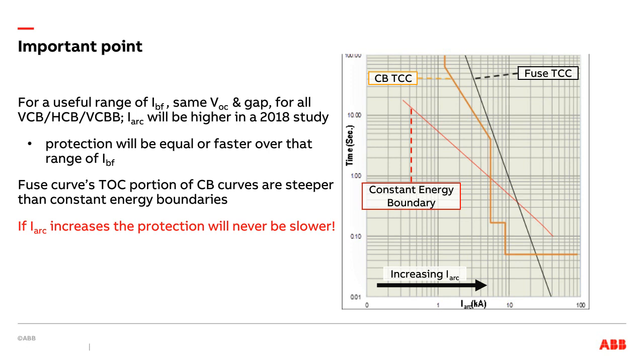You kind of need to analyze more than one, to make sure your protection can deal with the low current of one and with the high energy of the other. So you may need to do your analysis essentially twice. There is no clear answer that one is always more dangerous than the other. HCB is always more dangerous than VCB. That you can pretty much state clearly. But when you have VCBB in the mix, it makes it difficult because of the much higher arcing current. Hopefully that was clear as mud.